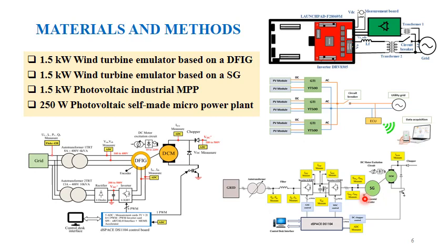The second one is a 1.5 kW wind turbine emulator based on a synchronous generator. A similar structure is used, but we need a back-to-back machine side converter and a grid side converter between the grid and the stator of the synchronous generator. The third one is a 1.5 kW photovoltaic industrial micropower plant, where six photovoltaic panels are connected — each two with one grid-tie inverter. The three grid-tie inverters are connected to the grid via a circuit breaker and to the energy communication unit.